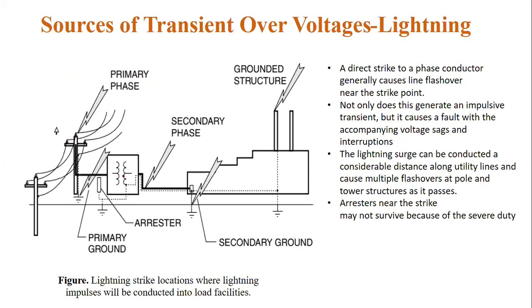At some amount, see this, some voltage is also passed to the primary of the transformer also. This is the transformer. Some amount goes to the transformer before an arrestor clears the fault.